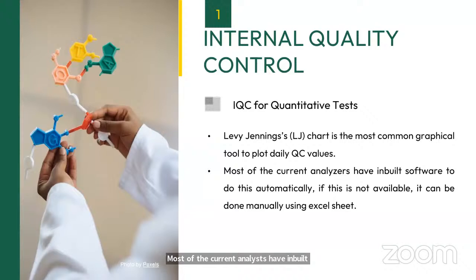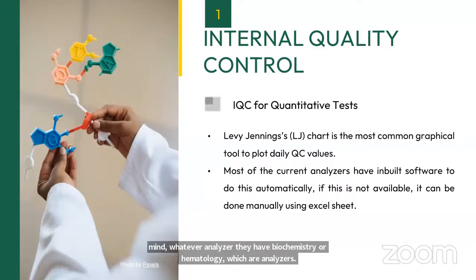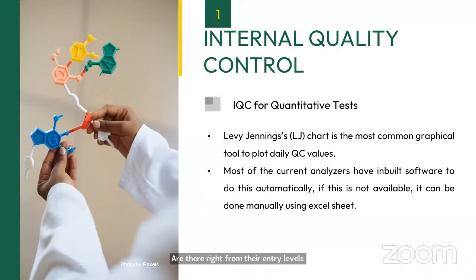So all the analyzers, even Mindray, whatever analyzers they have for biochemistry or hematology, right from their entry levels to high throughput analyzers, they have these graphical charts or software available inbuilt which performs the monitoring of your QC results. They plot appropriate LJ charts. They will also flag any type of outlier. They will also flag any other type of error, random errors, systematic errors. All those are plotted. If your equipment doesn't have this inbuilt software, it can be done manually using Excel sheets.